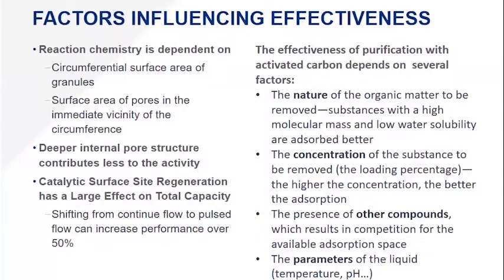This is that oil-and-water separation — polar versus nonpolar. The surface of activated carbon is nonpolar for the most part, and it attracts the organics. The concentration of the substance being removed also matters: the higher the concentration, the more of it we're going to remove. This is just about the odds of a molecule of something in water contacting the activated carbon. That's why we want dense structures that allow flow — we want those contaminants bouncing and making contact with the activated carbon. If there's too much room, it's not going to reach out into the water and grab things.